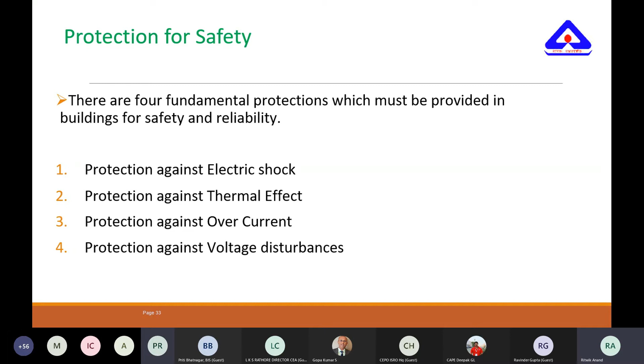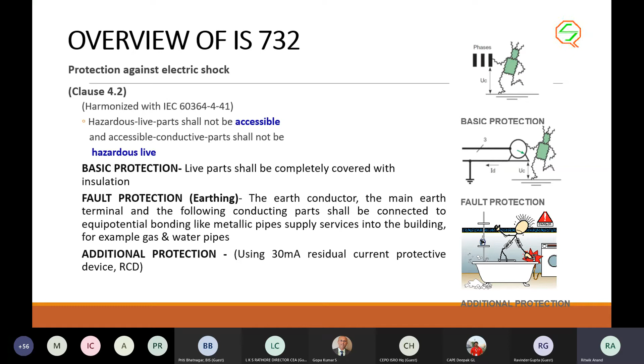So in electric shock, there are basically 3 kinds of protection given. The first one is basic protection, in which the live parts are required to be covered through insulation. Then there is fault protection, in which we use earthing and equipotential bonding. And there are also additional protection measures where 30 milliampere RCDs are required to be used in electrical installation.